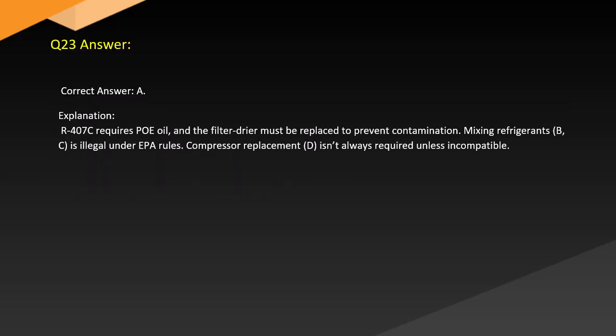Answer. Correct answer: A. Explanation. R407C requires POE oil and the filter dryer must be replaced to prevent contamination. Mixing refrigerants, B and C, is illegal under EPA rules. Compressor replacement D isn't always required unless incompatible.